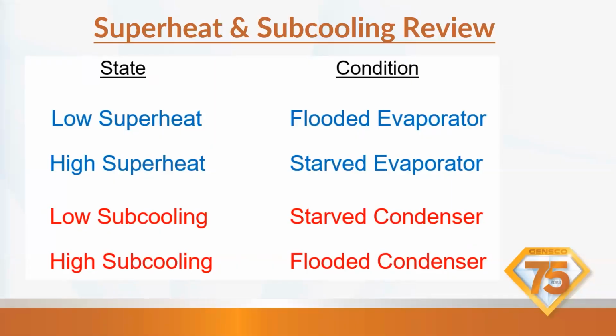We can go over, kind of, if we got a low superheat, it's a great graph that simplifies it a little bit. So if we have low superheat, if we're taking our superheat and we're at 5 degrees superheat, we have a flooded evaporator. So we're overcharged, possibly, that we have too much refrigerant in there and we're flooding the evaporator, not giving it enough time. Could be a metering device issue too. If we have a high superheat, we have a starved evaporator, not enough refrigerant. So the higher the superheat, we might have to add refrigerant.